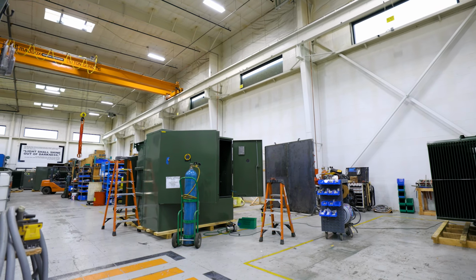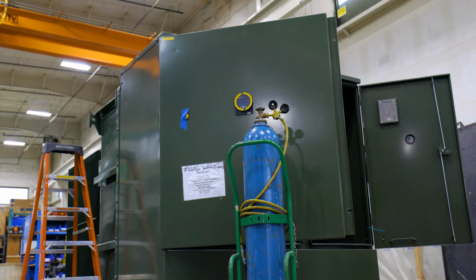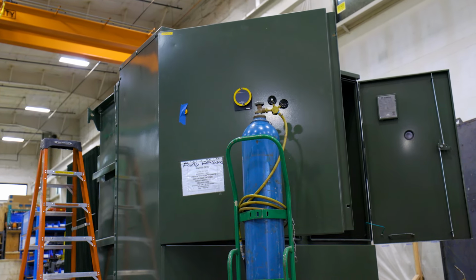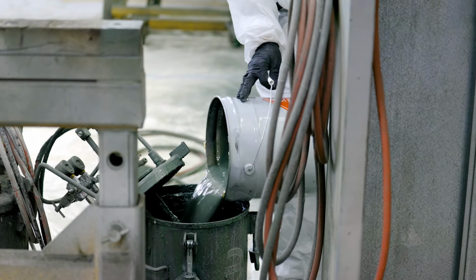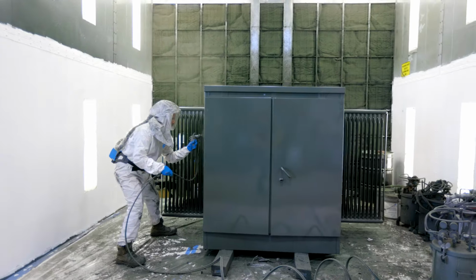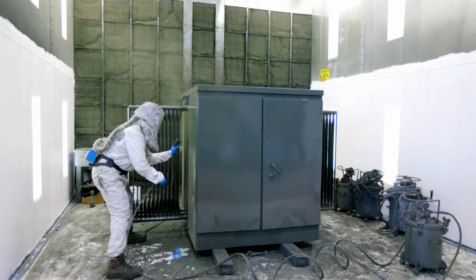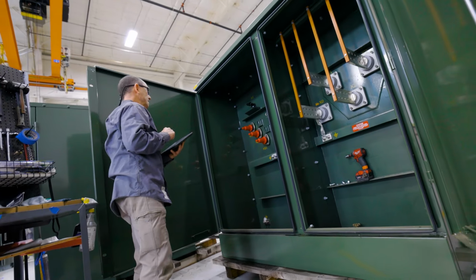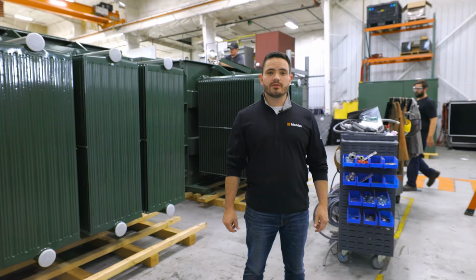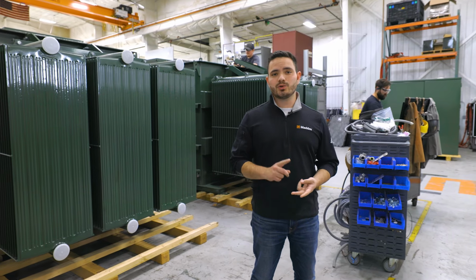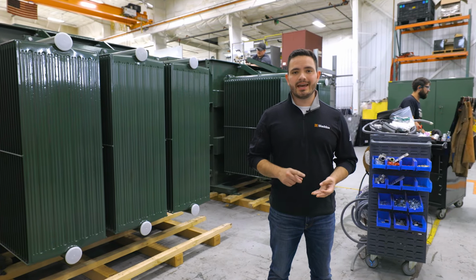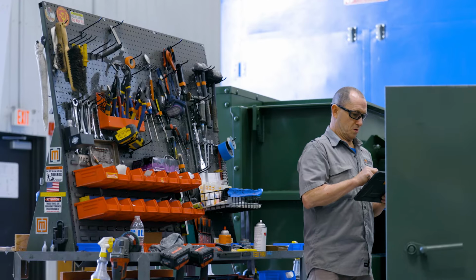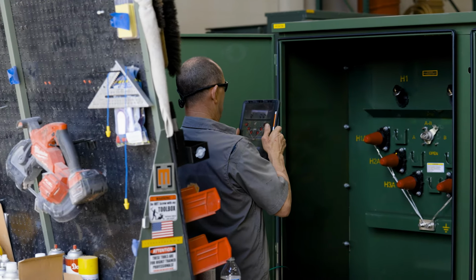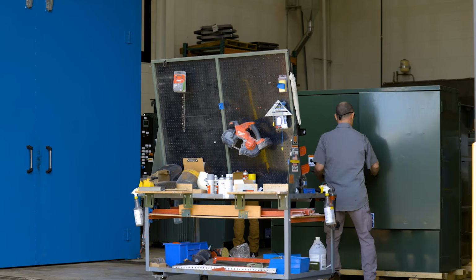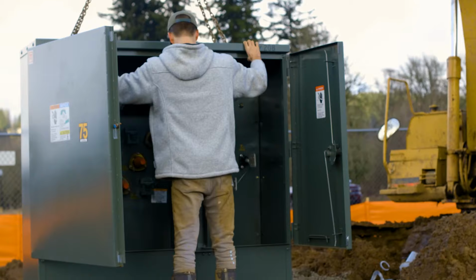Once the unit has passed final testing, we'll leave the tank under pressure overnight to ensure the unit is completely free of leaks. Then we sand, prep, and paint the tank with approximately 5 mils of high-quality paint so that it not only works like new, it looks like new as well. Next, the unit is run through our rigorous 45-point QC process. They check everything from radiator bracing to oil level, paint condition, and connection tightness. The results are logged into our system and kept on file for every single unit. Once the paint is dried, the transformer is shipped out and redeployed to the grid.